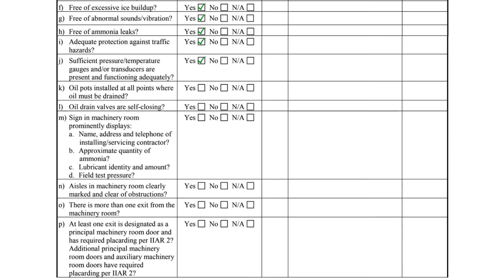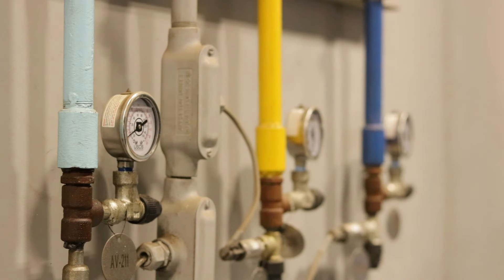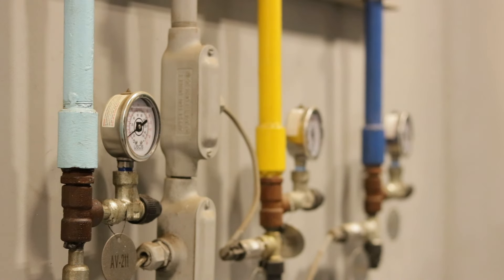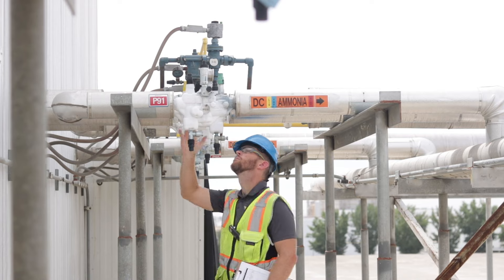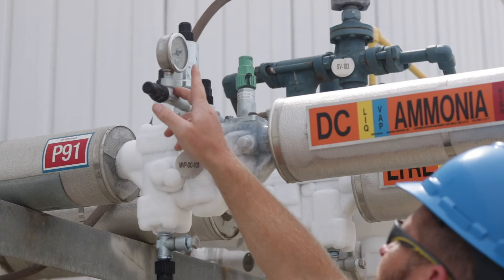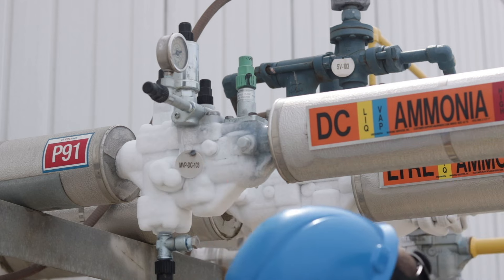All equipment must have sufficient instrumentation for monitoring the operating conditions per item J in the checklist. Most of the instrumentation for monitoring equipment will be located inside the machinery room, but the evaporator's pressure gauges are often located on the valve groups, which could be located near the evaporator or on the roof.